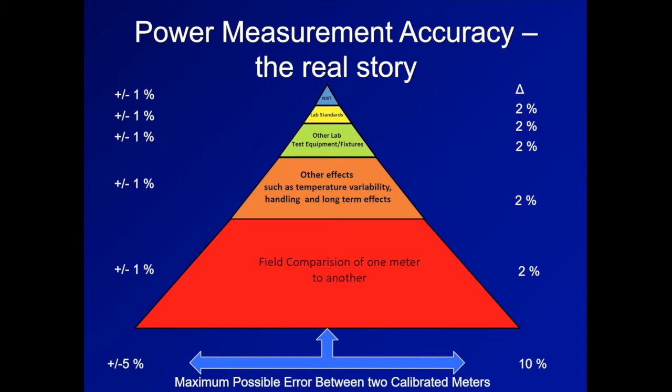So, the National Institute of Standards and Technology has developed procedures for measuring RF power or calibrating RF power measurement devices. And that's both sensors and inline devices and things like that. So, at the end of the day, the very best that they can guarantee, that they can tell you that the device that you send them for calibration is to the standard that they use is 1%.